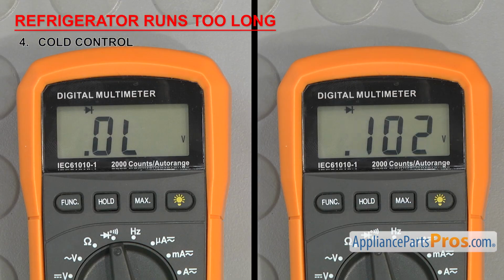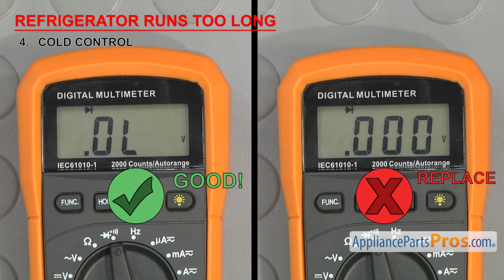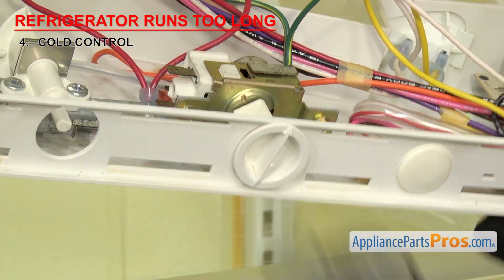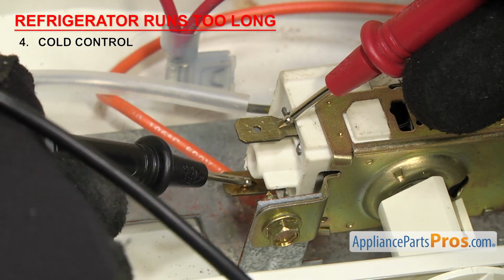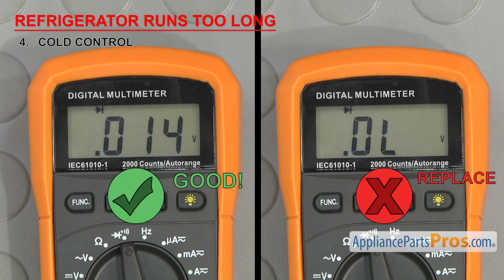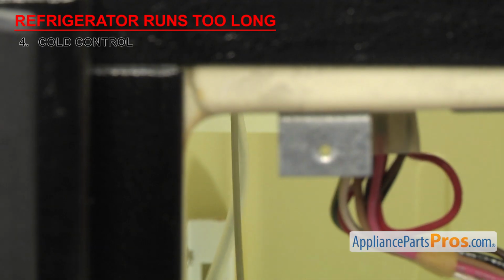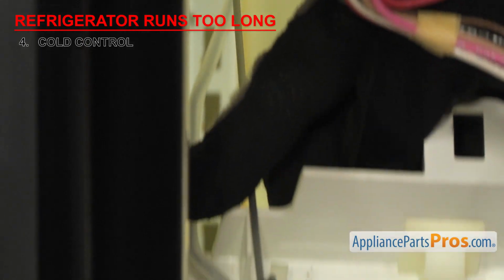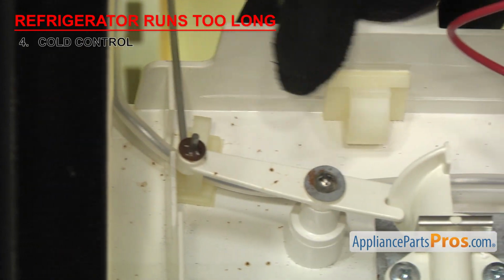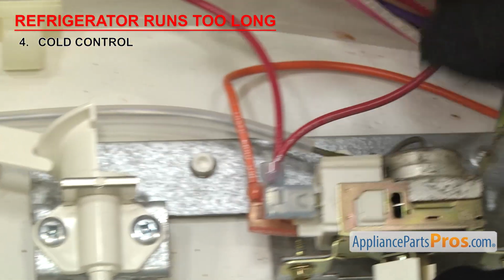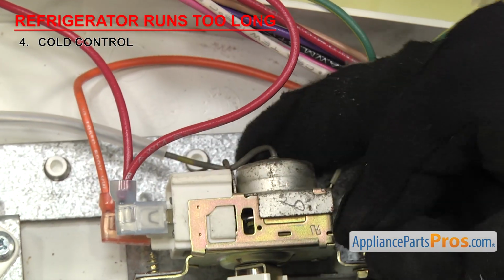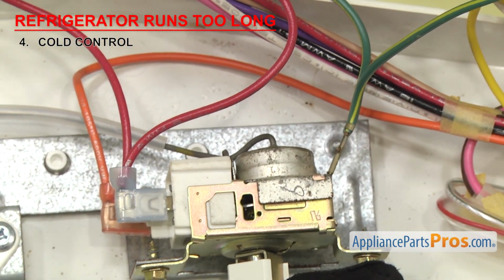Then touch a probe to each terminal. It should not have continuity in the off position. Then turn the control on. It should have continuity when you have it in the on position. If the control fails the continuity test, it'll have to be replaced. The last part of the control to check is the sensor bulb. Over time, they can rub against something or just fail and start leaking. If you see any damage or indications of oily residue along the bulb or where it mounts to the body of the control, then it'll have to be replaced.